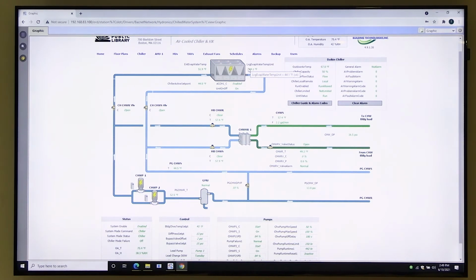Yeah, and that's kind of the idea with the heat exchanger. That valve is going to modulate and cool the water going across the other side of the heat exchanger, so we don't need to use the chiller if needed. There's no situation where you're going to have both the heat exchanger and the chiller operating. It's either one or the other.